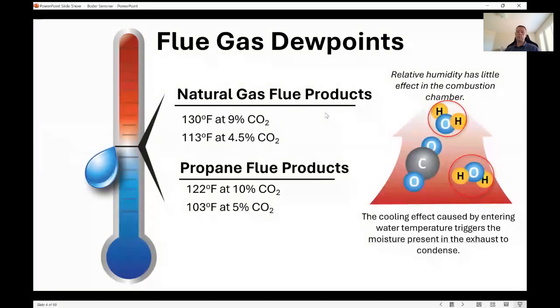So what happens with combustion? Well, stoichiometric combustion, or perfect combustion: you take a fuel source, and I'm going to talk about natural gas here, just because it's easiest. You take the natural gas, which is CH4, and combine it with oxygen from the air, O2. You get a source of ignition, a source of heat, something that gets that chemical reaction started. And ideally, what you're going to produce is water vapor and CO2. We know there's no such thing as true stoichiometric combustion, so you're going to get other stuff happening in there as well. But your main things are CO2 and H2O, and that water is in the form of a gas.